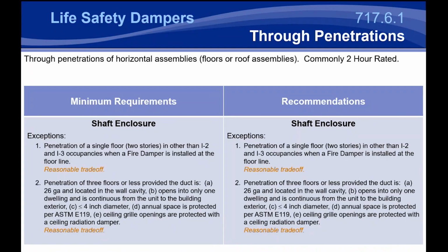So if you've got a fire damper installed in a horizontal stud floor, or wood or metal stud floor, I do recommend contacting, say, a damper manufacturer or someone to get some clarity on that, because there could be some issues with that. A regular fire damper wouldn't be able to be installed in that. So there's some things that I recommend. There may be some options available where you separate that load bearing floor assembly, but for the most part, you're going to have to put a damper in that.